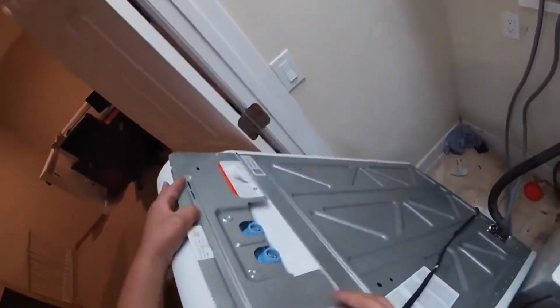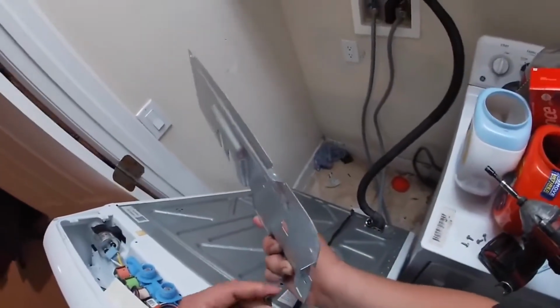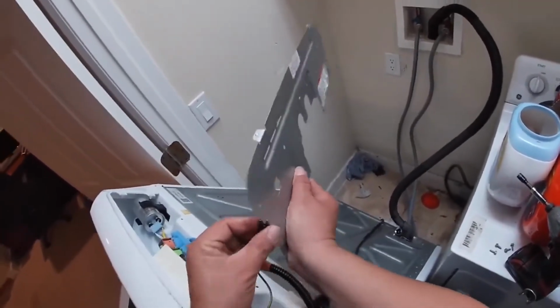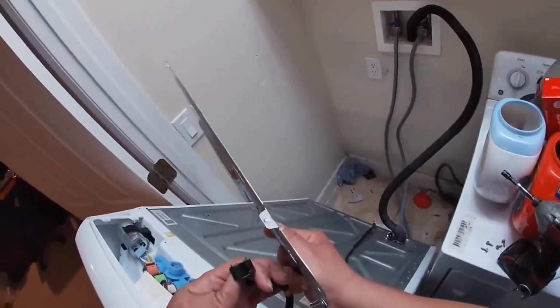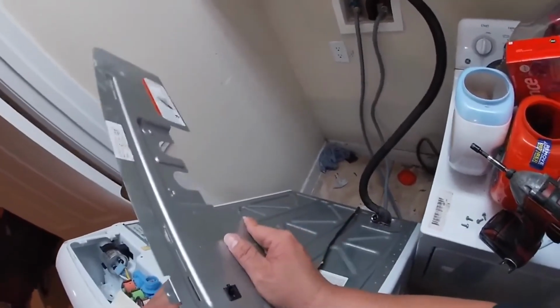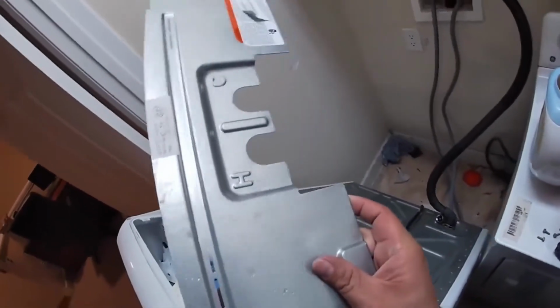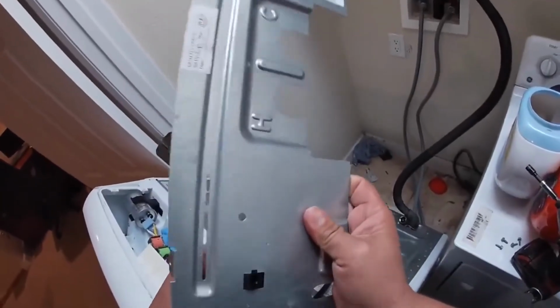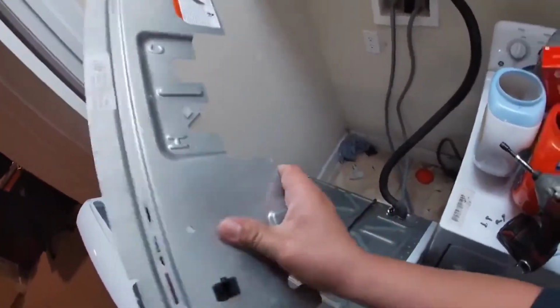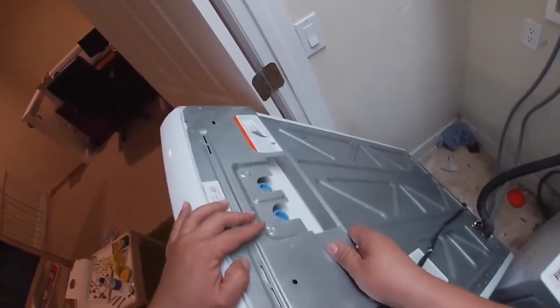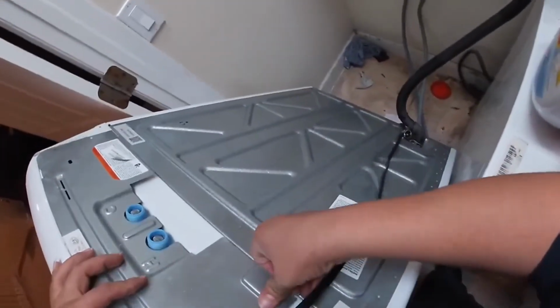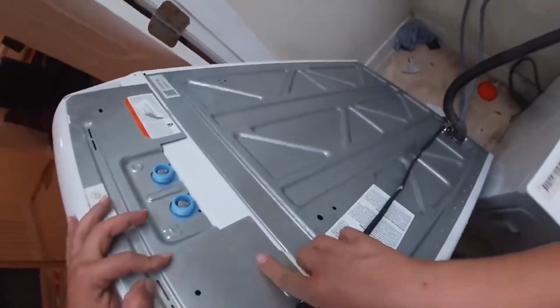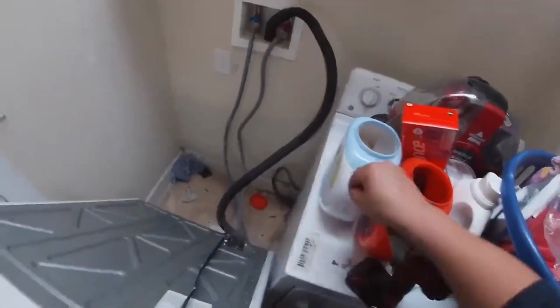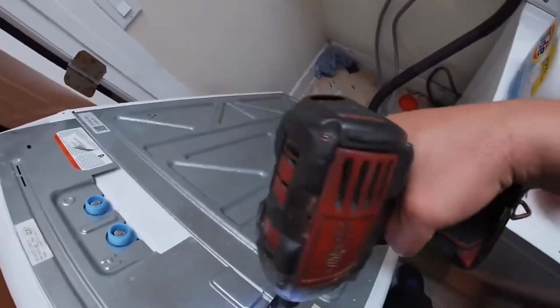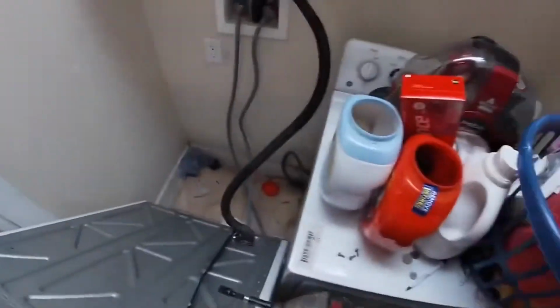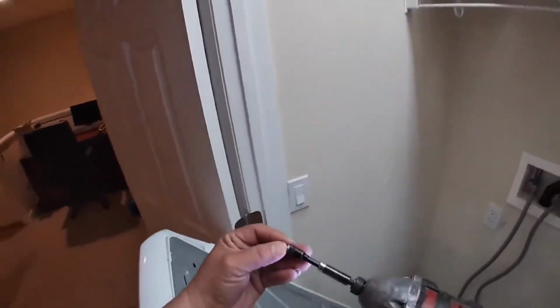This is the panel I was talking about. You will not necessarily have to remove it, you only remove the 2 screws, on the left and right side of the plastic panel. But I also removed this metal panel just to get a better view of the board, because the paperwork suggested checking the pressure tube on the board to make sure it wasn't clogged, so I decided to remove it. You don't really have to remove this piece, but if you want to work better and have a better view of the computer board, you can remove it. It's about 4 or 5 screws on the metal panel, and the 2 screws on the left hand side plastic display panel.